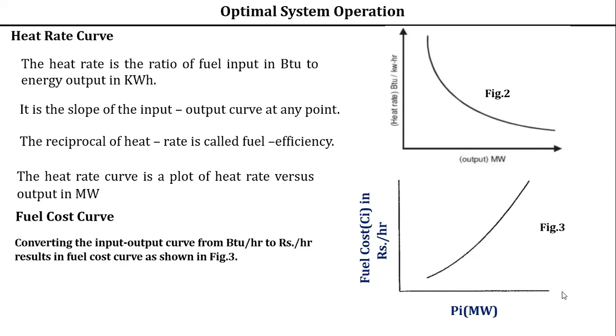So this x-axis is P_i, megawatts. But what is on the y-axis? It is fuel cost. Fuel cost is represented by C suffix i. C means it is a cost, C_i means cost of the ith generator. So what is the unit here? It is rupees per hour. And it is almost similar to your input curve. However, fuel cost increases much more rapidly as compared to your input output curve. So please remember these waveforms while explaining this. The heat rate curve is the reverse of your fuel input or fuel cost curve. That way you remember it.